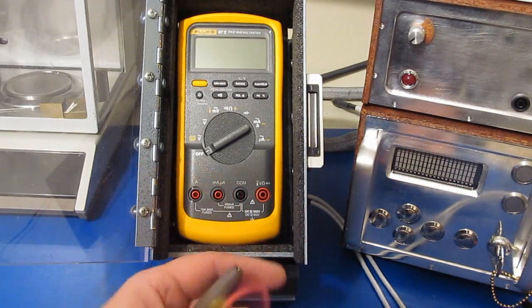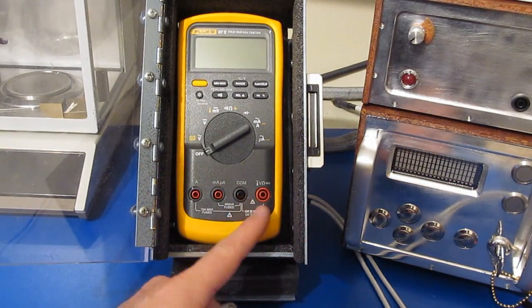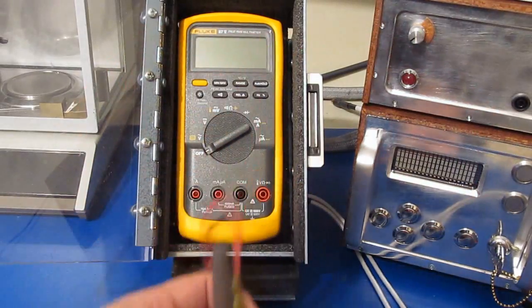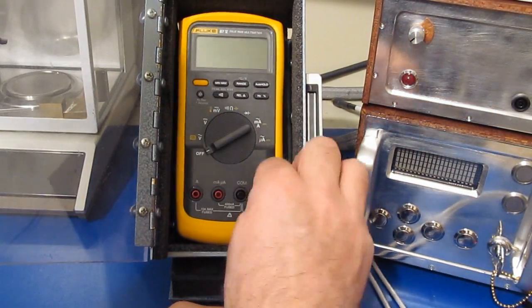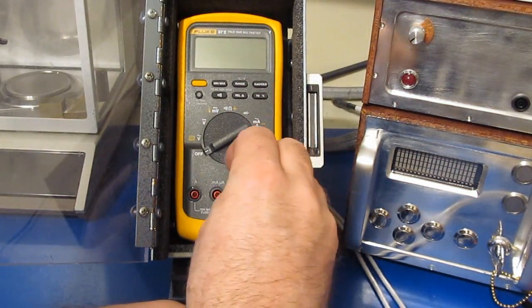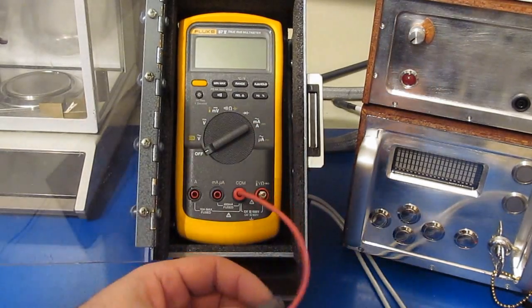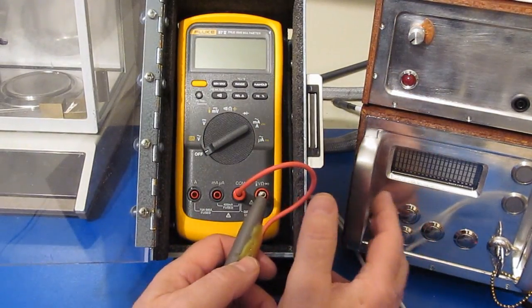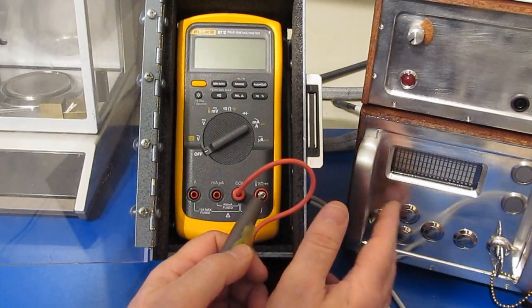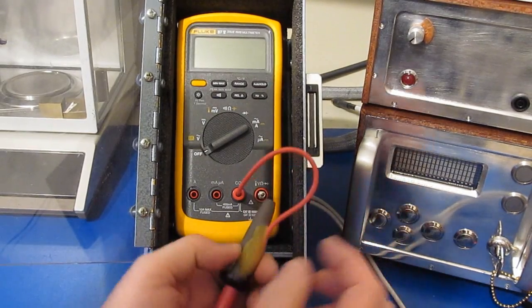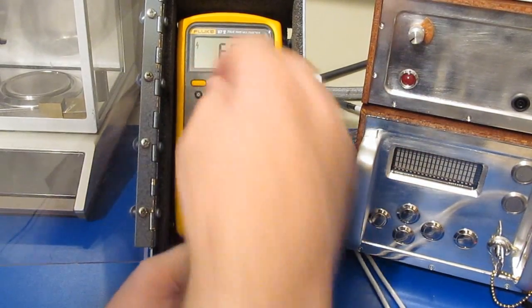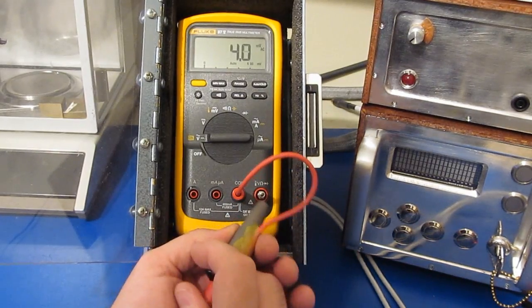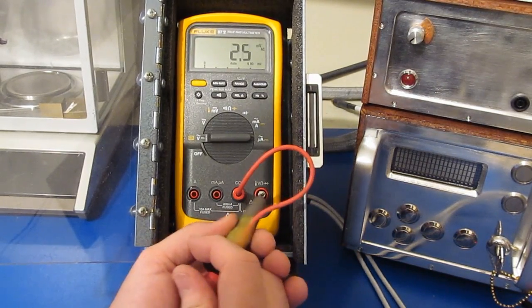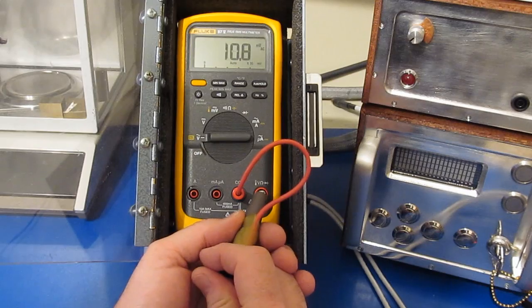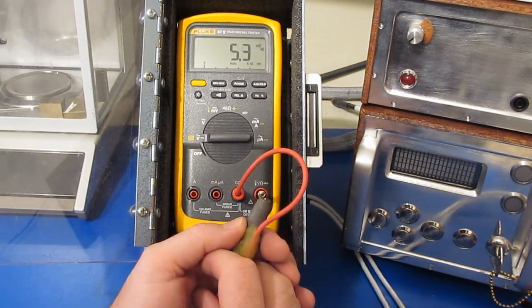So I thought I would static test the front end of this meter using this little grill starter like I had in the past. I'm not expecting this to have any effect on the meter whatsoever. When I previously looked at the 87Vs, I had never exposed those to my AC line test or the ESD testing, so let's give this a try. We'll be applying 5 pulses, both positive and negative, in each mode of the meter, and these will be a direct discharge.